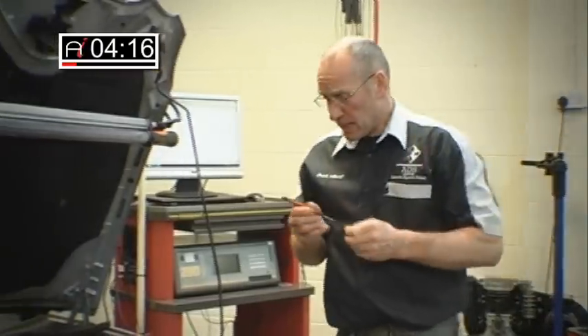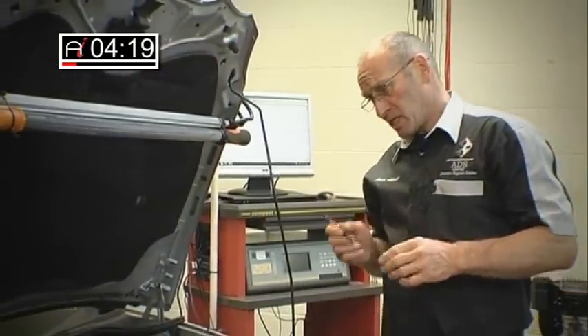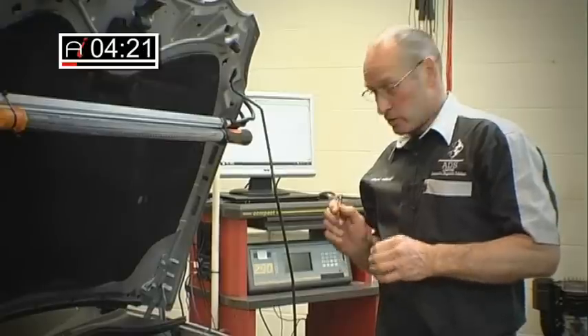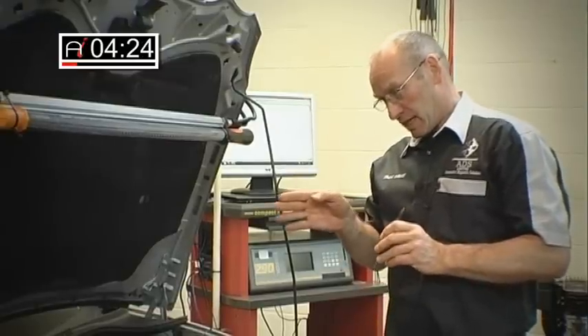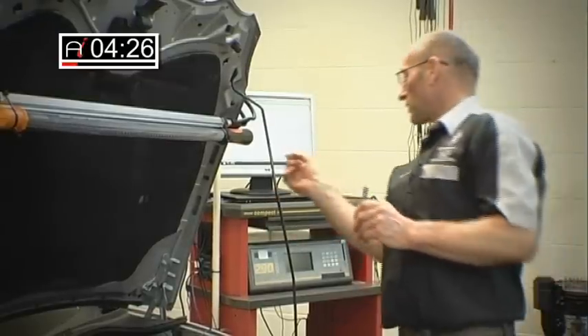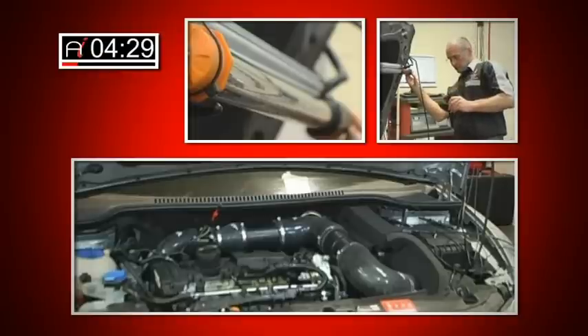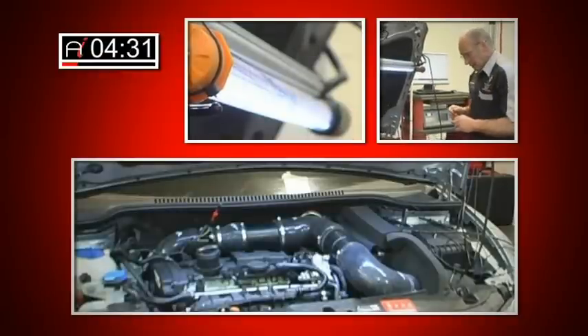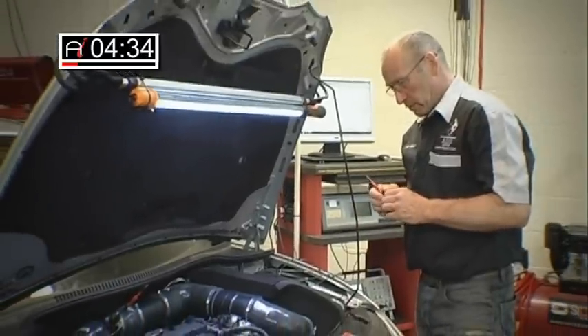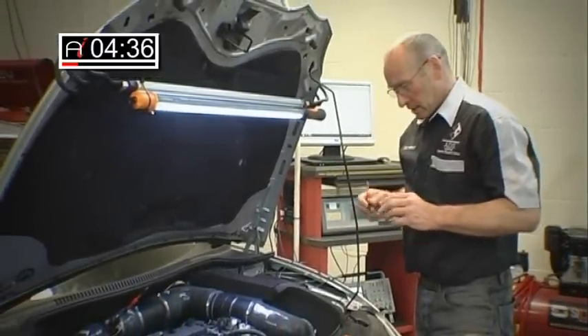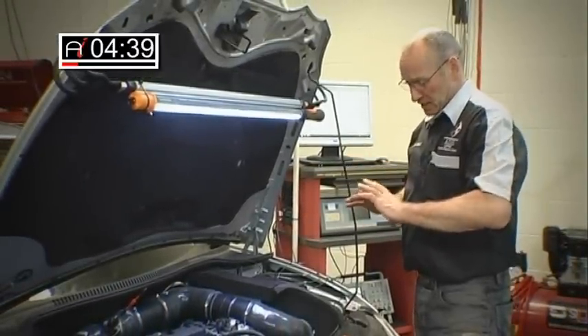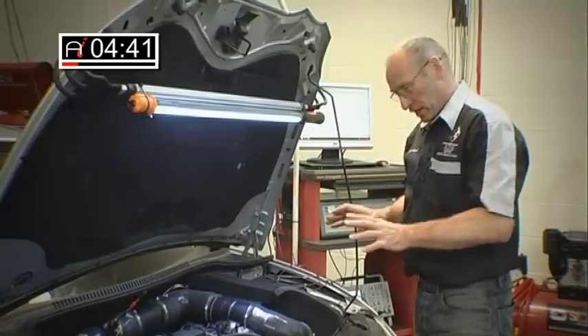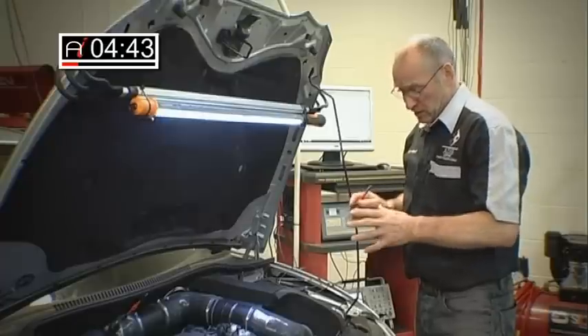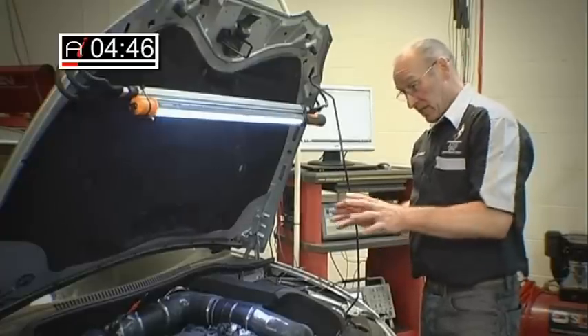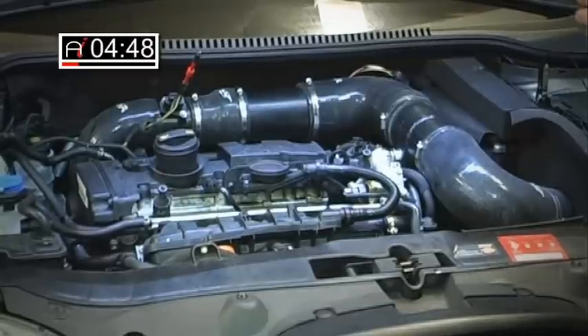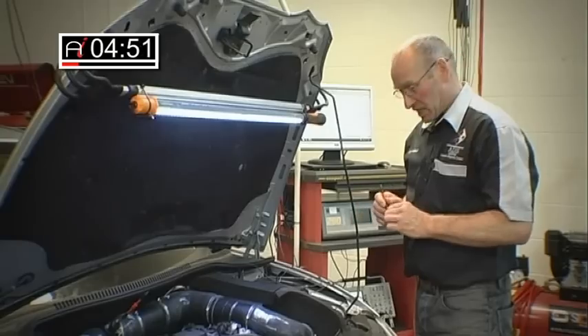I would also now like to take a second probe and use this as a floating ground reference. So I'm going to insert this in the center pin. It's a little bit dark, so I think we'll have a little bit more light. Lighting is one of these issues whereby we've tried a number of things in the past, and we found this type of light casts a fairly neutral, shadow-free light. We in diagnostics obviously want to see wire colour, connectivity, as well as illuminate the area. So we found this one of the better options when conducting testing.